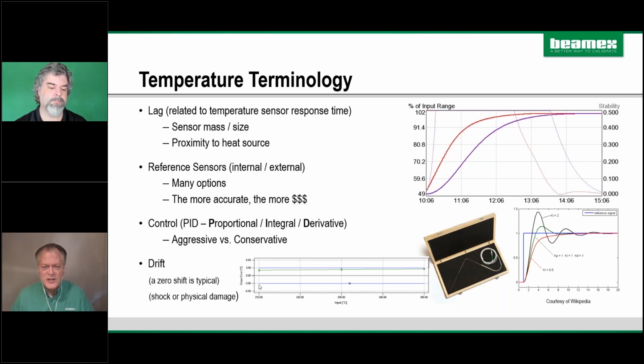So here's a graph. I know it's hard to see, but basically this probe with a tolerance of 3 degrees is somewhere around 2 degrees high, across the range. This is a very narrow range, but it's very typical of what you might see on a probe.